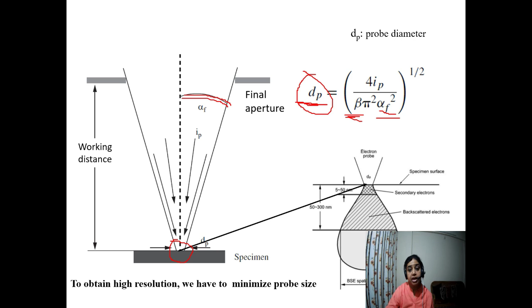Now, specimen preparation. Some precautions need to be taken for SEM preparation. We are going for topographical information. The moment I say topographical information, it means I am talking about the secondary electron, the inelastic electron. So for this, minimal sample preparation is required. First, you need to select your sample size so that it can be mounted on your sample stage. In the machine, you have to check the size of the sample stage. Now you have to remove sample contamination. Even if you touch it by hand, it will get contaminated. So you have to clean it very nicely.